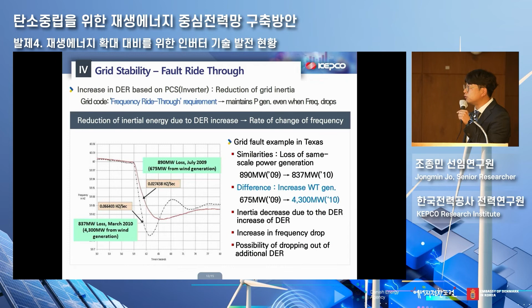There was a relevant case in Texas, and as Officer Pang Min-sun has briefly mentioned, this happened in the UK during a major blackout. A 400kV transmission line ground fault was caused by a lightning strike, creating an instantaneous voltage drop of 8 ms, and plants shut down and frequency dropped further.